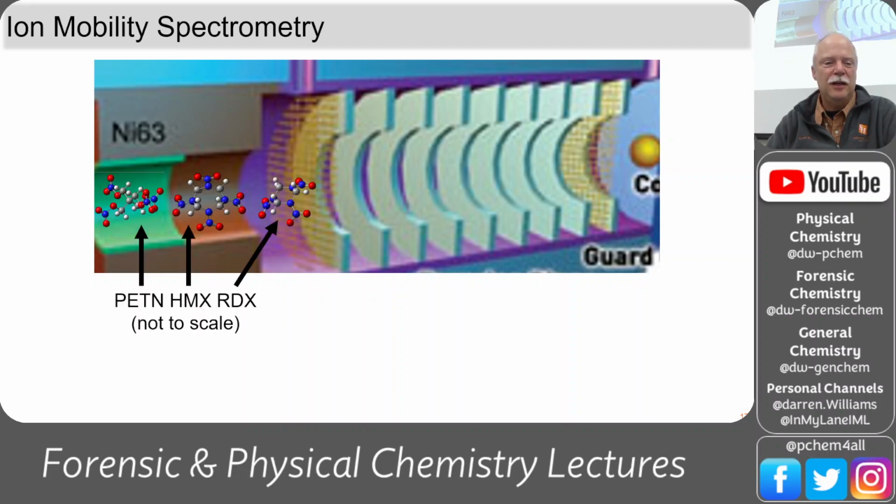So here's how it works. Most of the time in mass specs, you have a high voltage source to produce an electron beam, like electron ionization, and that beam of electrons will ionize the sample. So EI, electron ionization. But that comes with the cost of the bulky power supply and the power requirements for running the power supply. And so another way to produce high energy electrons is a radioactive substance.